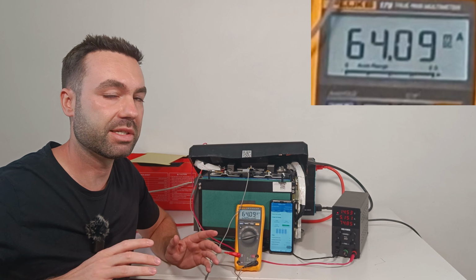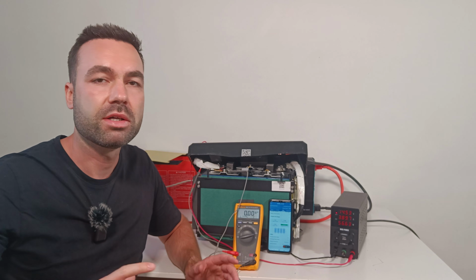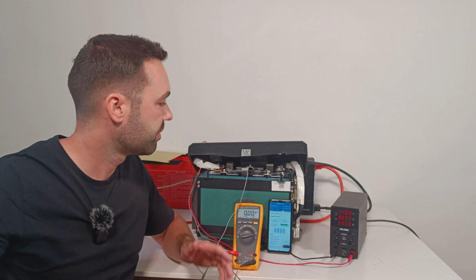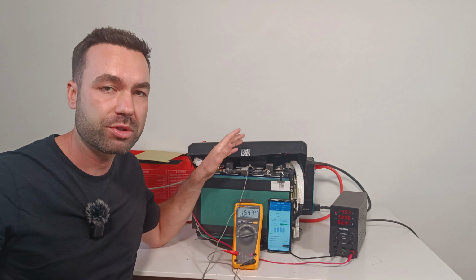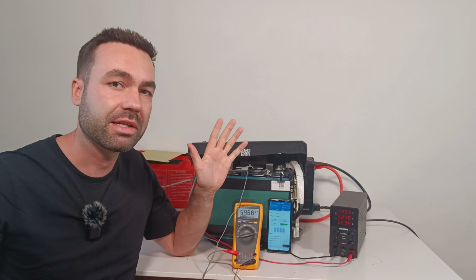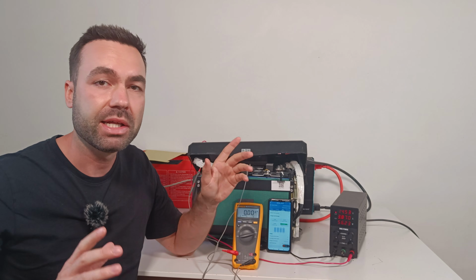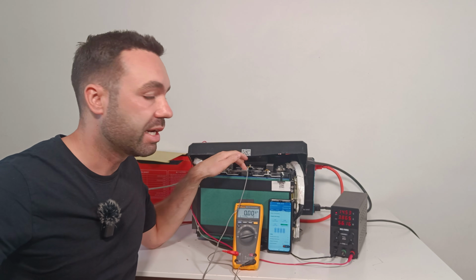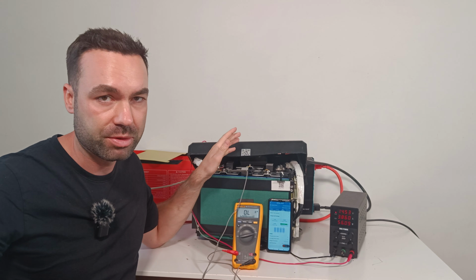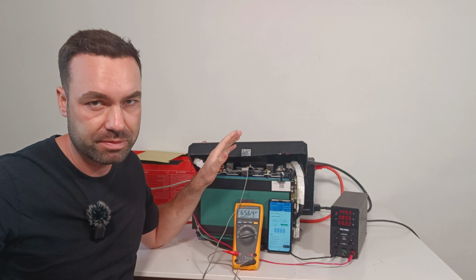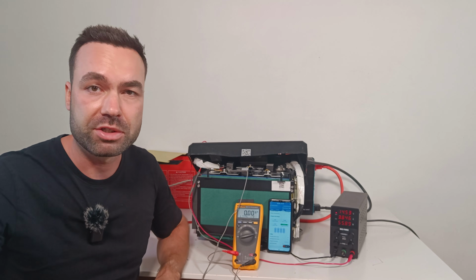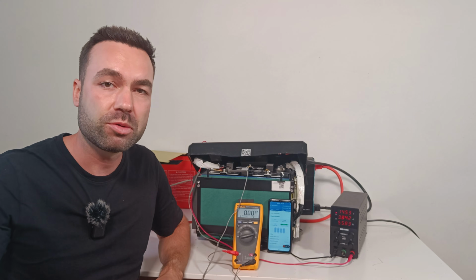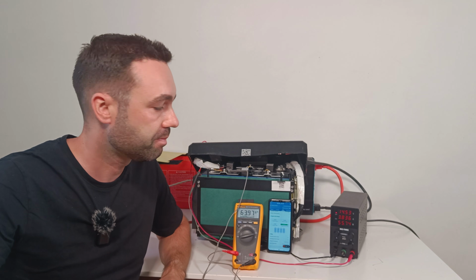So that's quite disappointing. So let's recap this review. It delivered 330 amp hours, 5% more than it's rated for. That's great. It delivered 200 amps continuous, that's great to see. And the overcurrent protection tripped when it was over 240 amps.